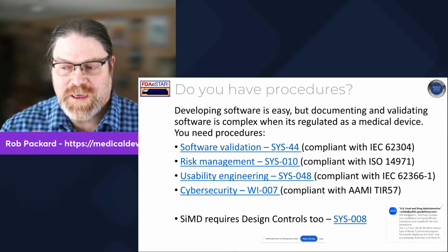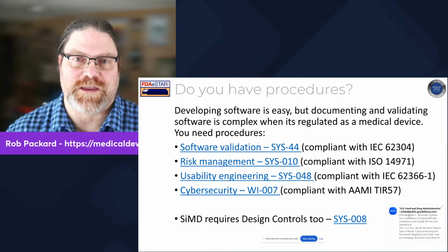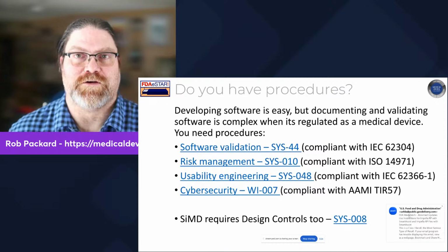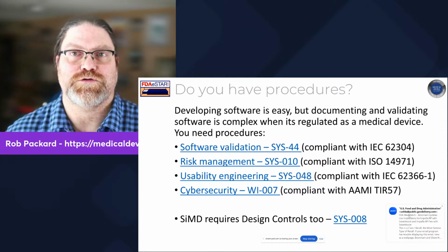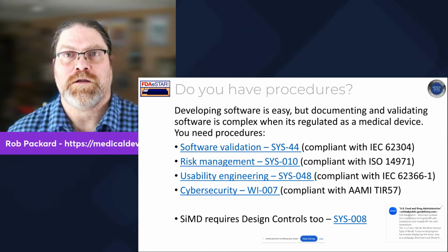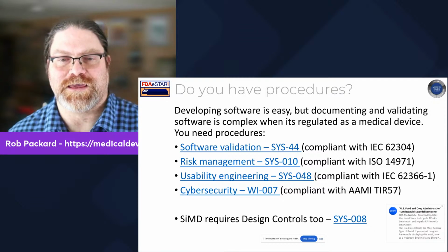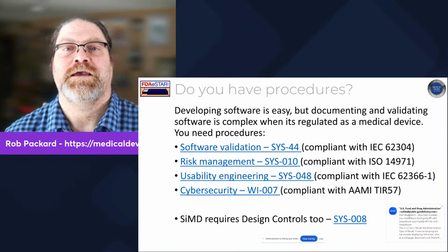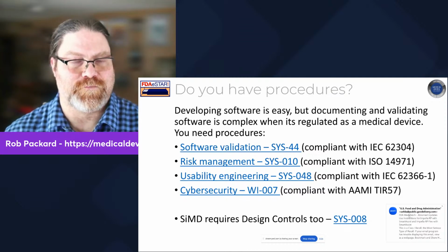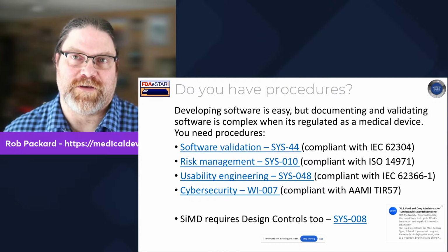The third thing you need is usability engineering. This is the IEC 62366-1 standard for usability engineering. That's a relatively new standard, and there are new guidance documents on usability and human factors. But the FDA has seen more and more, when you make small changes to software, you change the user interface, it becomes easier to cause inadvertently some use errors. So you need that piece too. And for almost all the new software submissions we're submitting, we have to submit usability validation.